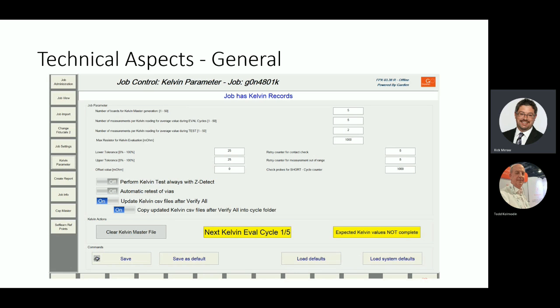When we're putting the probes on in our software, it's adjustable, but we go up to 5 readings. We take 5 readings on that pad the first time during master generation, just to make sure we're getting everything accurate and there's no poor contact. We take 5 readings, move to the next pad, take another 5 readings, and continue this for each set of measurements. When the first board is done, we move on to the next board.